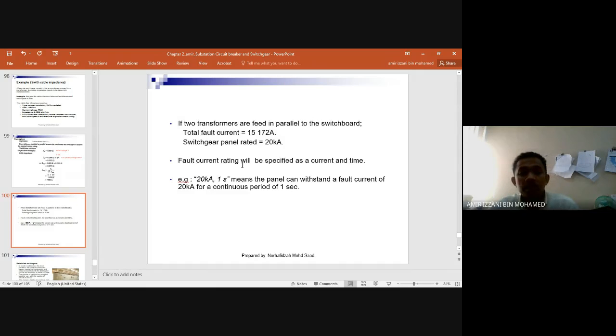Usually the current rating will be specified as a current and time, meaning how long the current can flow. For example, here it is 20 kiloamps for 1 second. So what does it mean? It means that 20 kiloamps current can flow only for 1 second. Okay, just a little calculation.